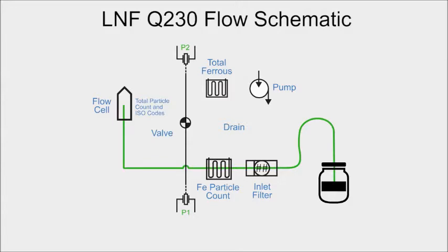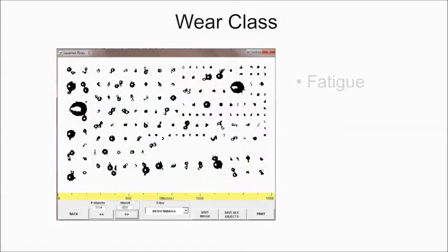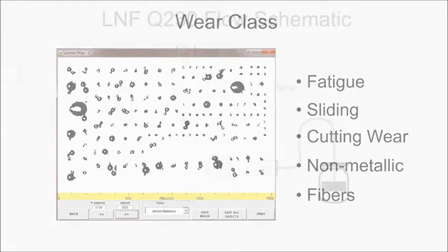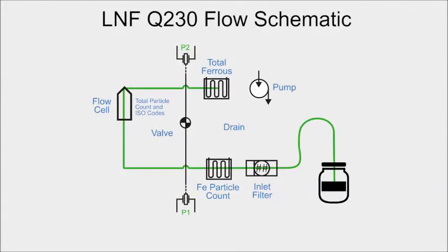This provides particle count and ISO codes, and also characterizes all particles greater than 25 microns into a wear class: either fatigue, sliding, or cutting wear, non-metallic, or fibers, based on the shape of the particles. Finally, the sample enters the second magnetometer, which measures total ferrous content in ppm.